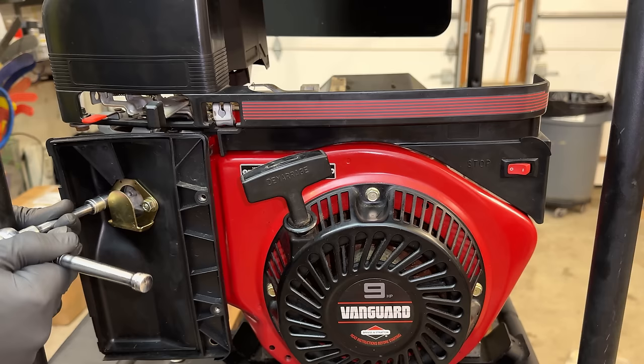Okay, let's bring it up to the max now. So we'll swap out the 500 for 2000. So now we're at 4000 watts. The engine's definitely struggling a bit. Let's try 4,500, 5,000. So we're at the rated load.